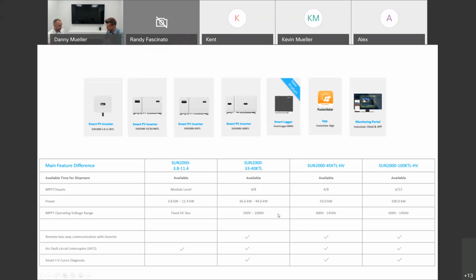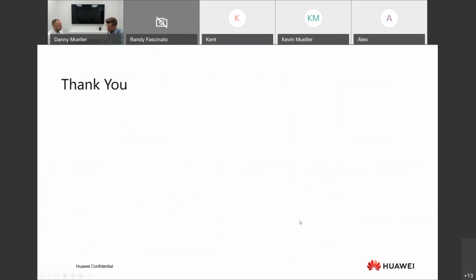Then the 45 KTL, as we talked about, and then the last is hidden behind a window here. That's the Sun 2000 100 KTL HV, the 100 kilowatt unit that they have. Similar voltage window as the 45 KTL and all the same features. The only major difference is it has 6 MPPTs and 12 inputs as opposed to the 4 MPPT 8 string of the 45 KTL. And the major downside, as Danny already mentioned, is the 800 volt AC concept, which is not standard. So all the breakers, electrical cabinets, and wires you buy, everything has to be rated for 800 volts or higher. Unfortunately, the cost savings on the inverter, which is maybe 0.4 cents cheaper or something like that, is eaten up multiple times over by non-off-the-shelf components, which are extremely expensive compared to just a regular 600 volt switch, fuse, AC gear, and so on.